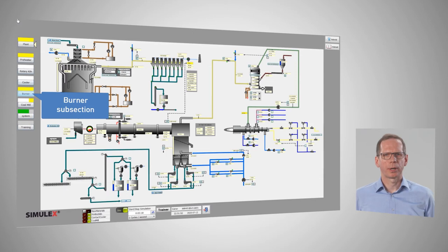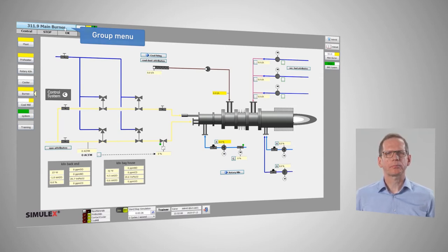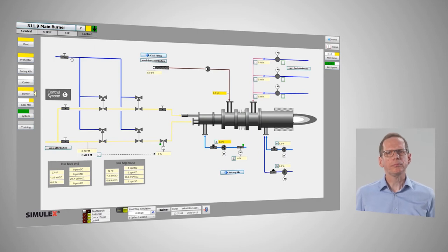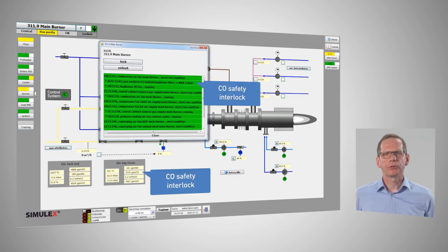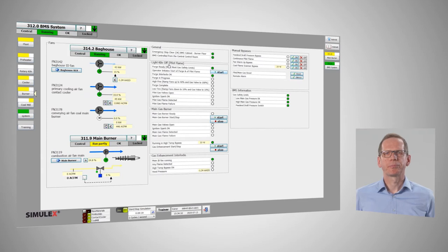Let us now look at startup sequences. All major equipment of a plant can be simulated, including startup sequences or process interlocks. You can start equipment in the same order as you would do in a real plant environment. As an example for incorporated sequences, the burner safety interlock due to high CO measurement in the exit gas can be mentioned. Moreover, we recently also implemented a complete burner management system in a client project. This allows the startup of a burner including all steps from purging to ramping and ignition. Related interlocks like flame detection are also available.